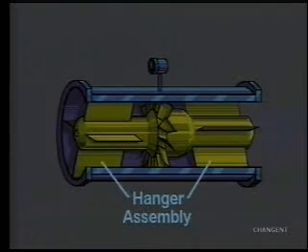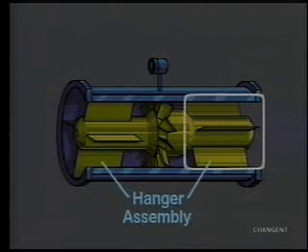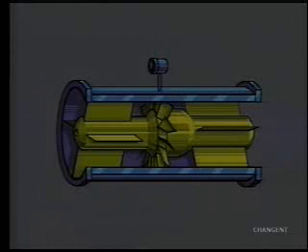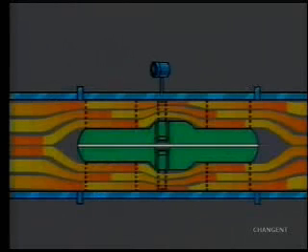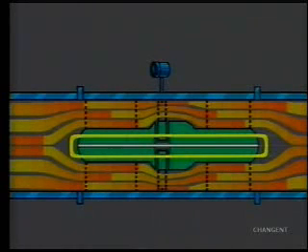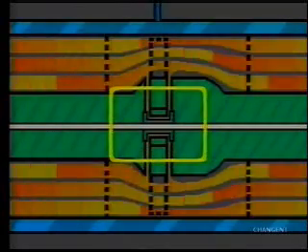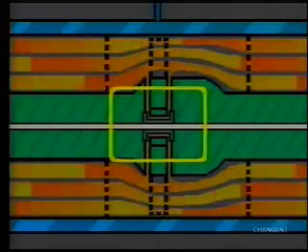The turbine rotor is mounted on a shaft by an up and downstream hanger assembly. Although these hangers might resemble straightening vanes, they do not perform this function. The turbine rotor blades are set at a predetermined angle. This angle relates the flowing stream, angular velocity of the rotor, and the frequency of the meter. The rotor rotates on the center line shaft by means of a bearing. This bearing is either lubricated by the meter fluid itself or permanently sealed.